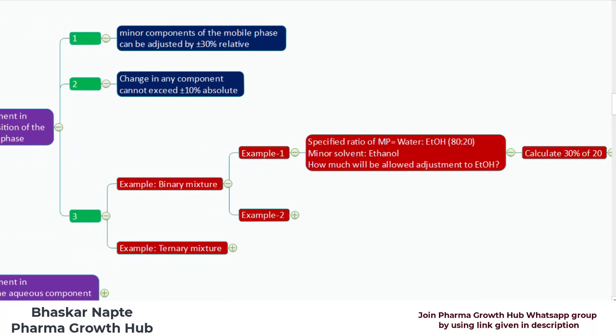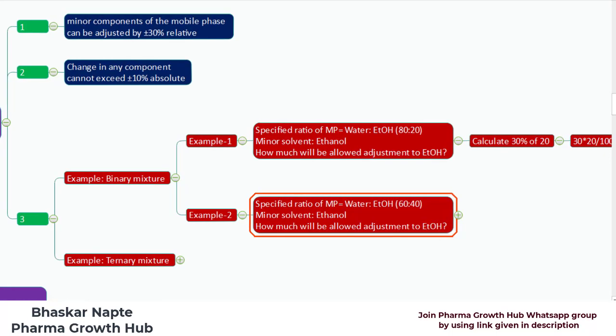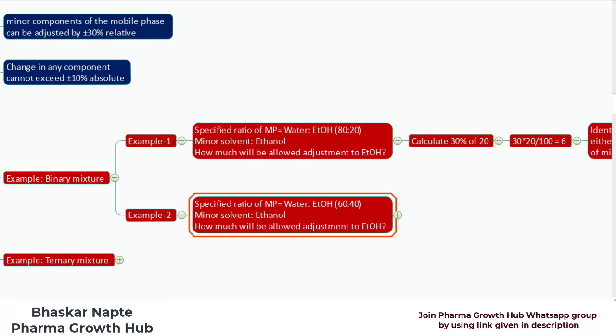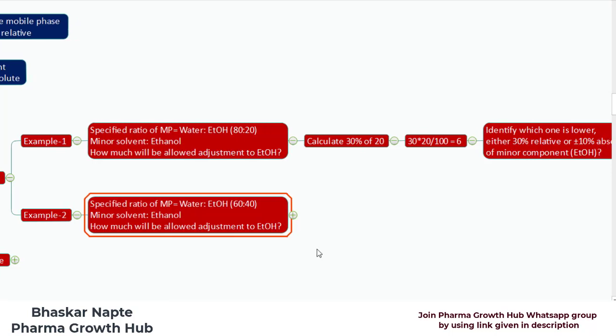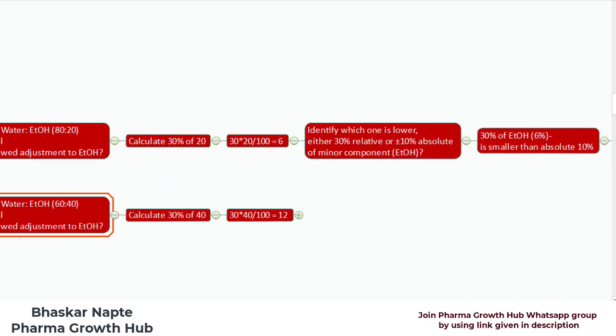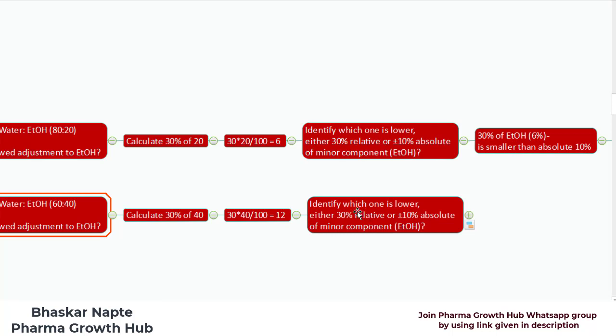This is for the binary mixture. I will also explain another example for binary composition. In this case, let us assume the mobile phase consists of water 60 and ethanol 40. The minor solvent is ethanol and you need to calculate the allowable change in the quantity of ethanol. Calculate 30% of 40 — the 40 coming from ethanol, which is the minor component. So 30% of 40 becomes 12. Now identify whether 30% relative or 10% absolute is lower. In this case, the 30% of ethanol is actually 12%, which is more than the absolute 10%.